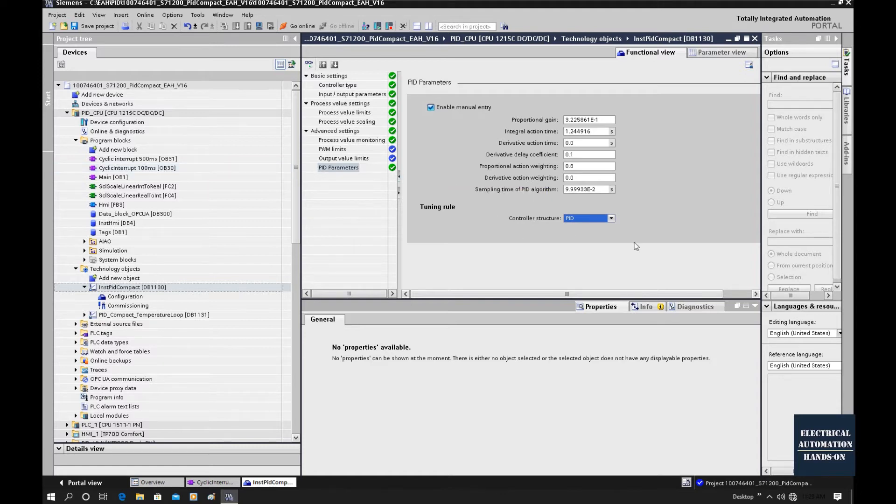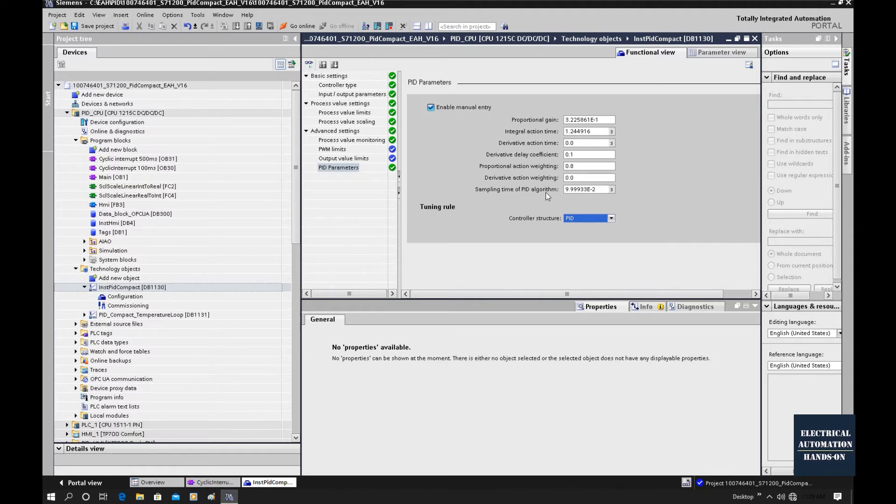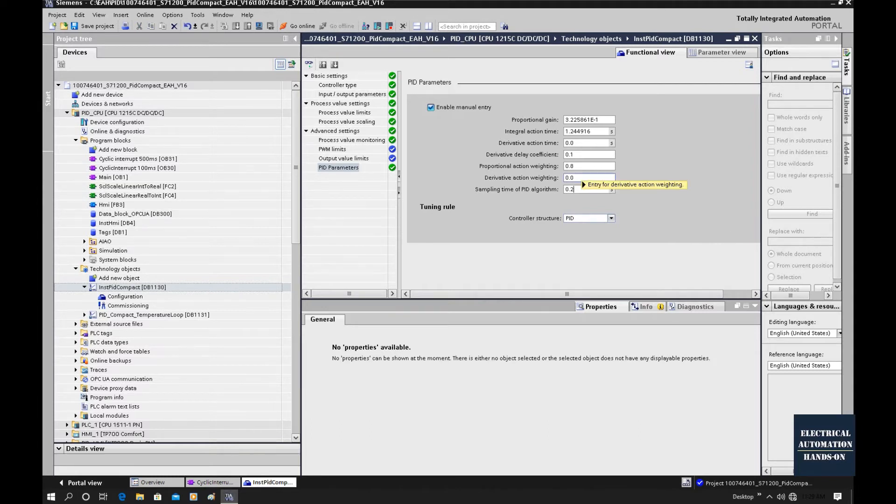Since this is a temperature control loop, our sample time does not need to be so fast. I will set 0.5 seconds, half a second. With this 100 milliseconds cyclical call, every five times it calls this PID.